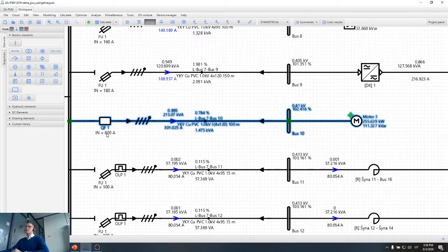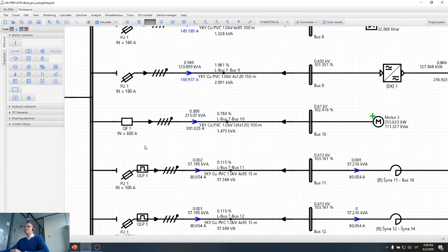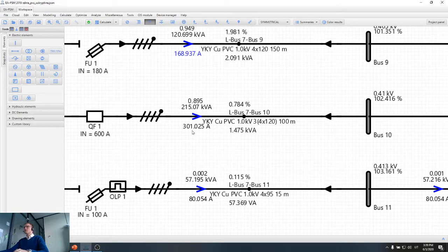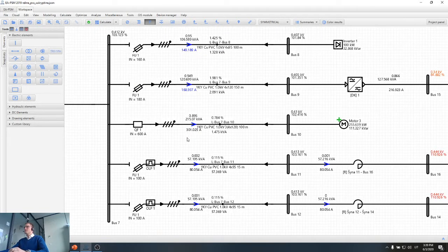Therefore fuses are not recommended, and for motor protection we recommend either motor circuit breakers, or just normal circuit breakers with electromagnetic tripping characteristic. So in this case I will use one normal circuit breaker of 600 amps. We can see that our motor current is 300 amps in normal operation. This is because the motor is not fully loaded. Let's open the breaker.